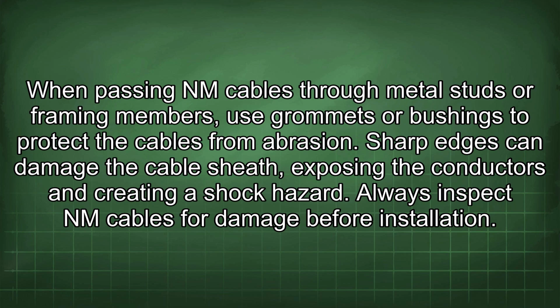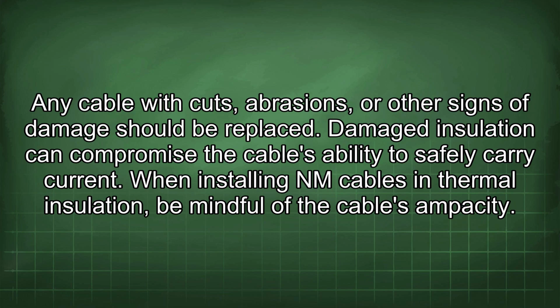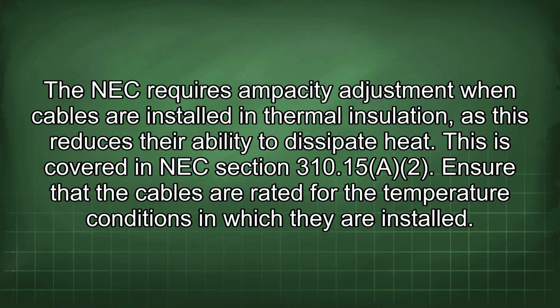Always inspect NM cables for damage before installation. Any cable with cuts, abrasions, or other signs of damage should be replaced. Damaged insulation can compromise the cable's ability to safely carry current. When installing NM cables in thermal insulation, be mindful of the cable's ampacity. The NEC requires ampacity adjustment when cables are installed in thermal insulation, as this reduces their ability to dissipate heat. This is covered in NEC Section 310.15(A)(2).